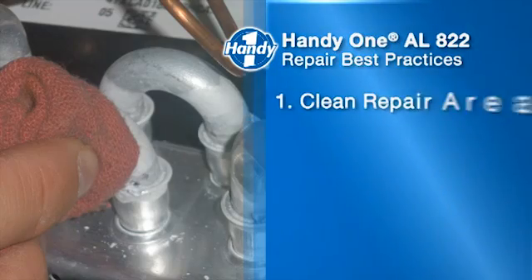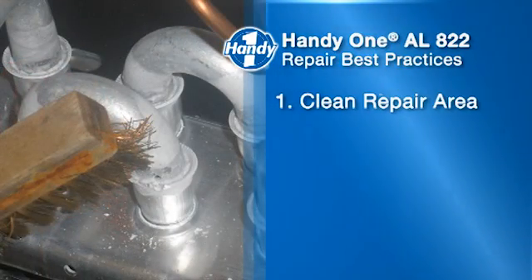Here's how to perform a repair. Clean the repair area to remove any dirt and oil that may prevent the brazing filler metal from adhering to the surface.